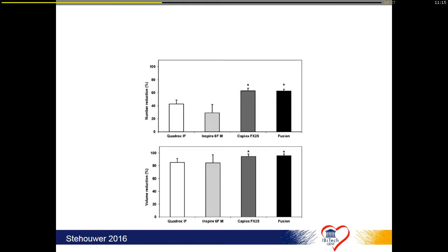And then, of course, almost every study performed will show you that there is a benefit of this integrated filtration. However, I'm not always convinced that the hypothesis or the conclusions made by some authors are completely correct. For example, what you see here, those people state that if you look at those two oxygenators, they work as a depth filter, and those two work more as a screen filter. This is not true. It can't be true. All of them work like a depth filter.